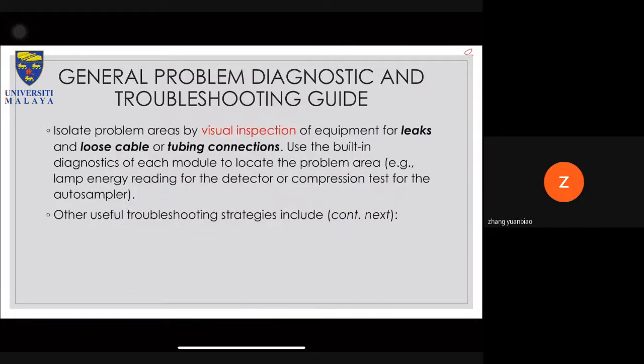Okay, so what you can also do is isolate the problem by visual inspection of the equipment, especially for leaks. This is in case the pressure goes too low, or if you are using an auto collector system whereby you ask the machine to collect 5 mL in a Falcon tube, but once you get the Falcon tube, the volume there is just 2 or 3 mL. Then there might be a leak, because you are expecting 5 mL in your collection tube, but what you are seeing is just 2 mL. Okay, so this can be an indicator that there might be a leak.